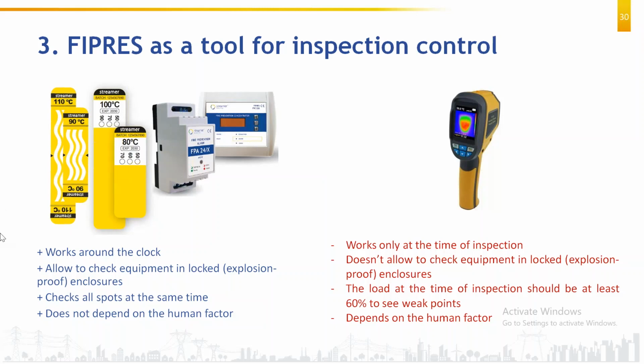FIPRES checks all spots at the same time. Thermography doesn't check all spots at the same time. You will open one cabinet, check that, then open the second cabinet, check that. Secondly, for checking one particular terminal to be at a certain abnormal temperature, the load on that particular terminal should be at least 60%, which is not always possible.